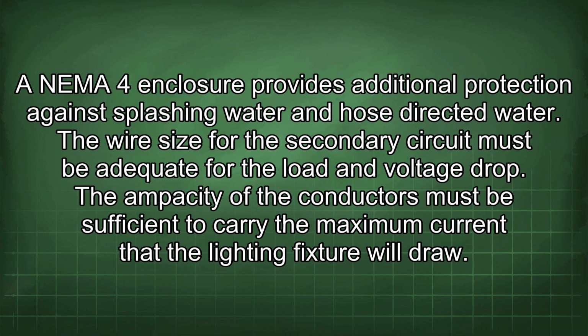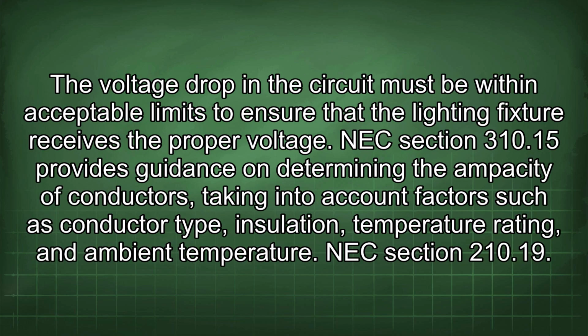The wire size for the secondary circuit must be adequate for the load and voltage drop. The ampacity of the conductors must be sufficient to carry the maximum current that the lighting fixture will draw. The voltage drop in the circuit must be within acceptable limits to ensure that the lighting fixture receives the proper voltage. NEC Section 310.15 provides guidance on determining the ampacity of conductors, taking into account factors such as conductor type, insulation, temperature rating, and ambient temperature.